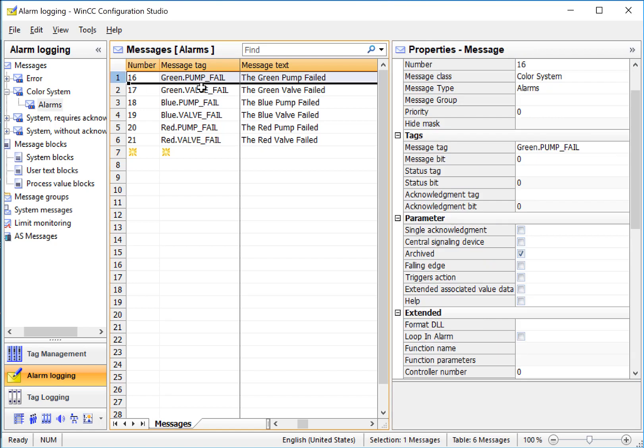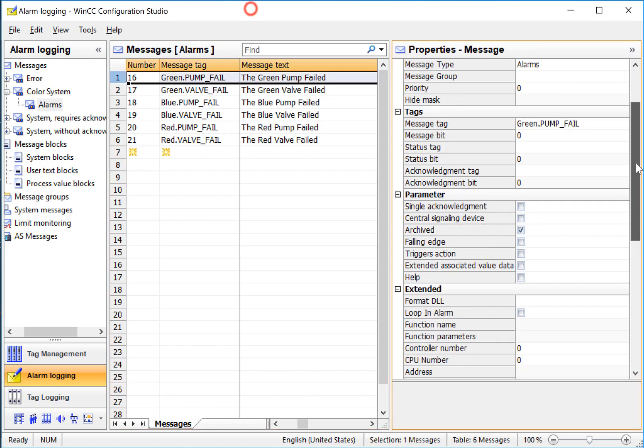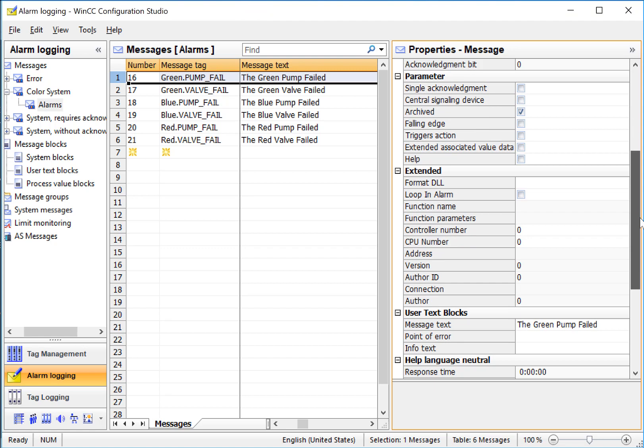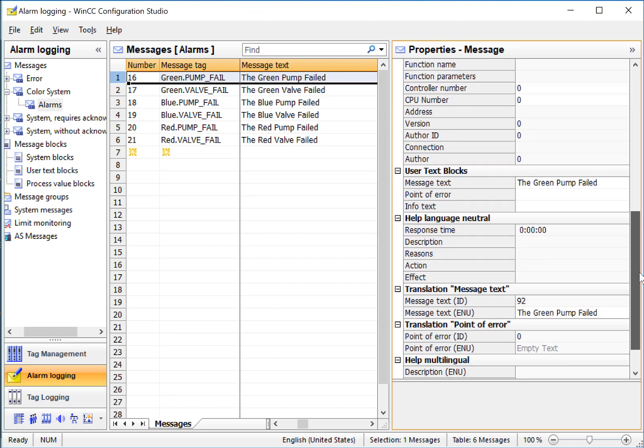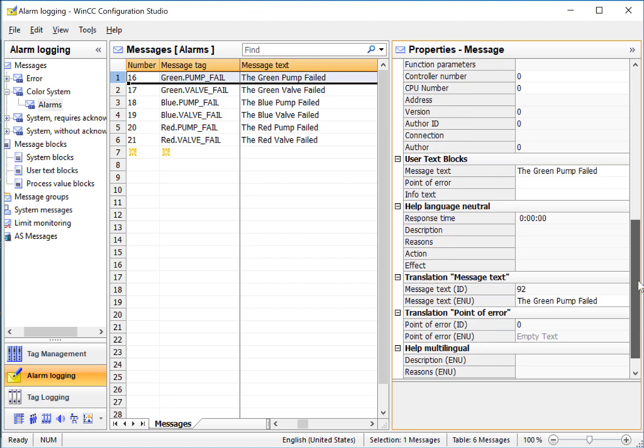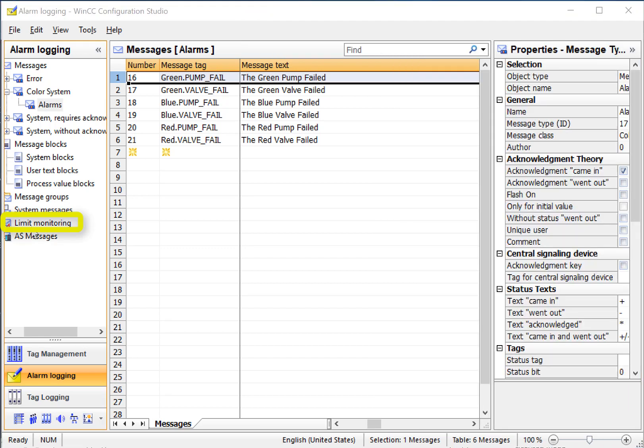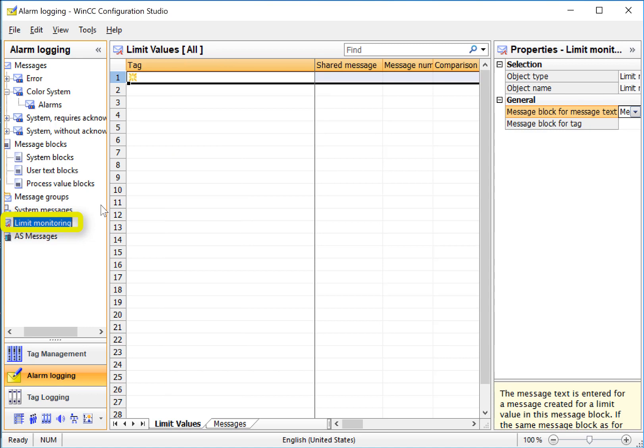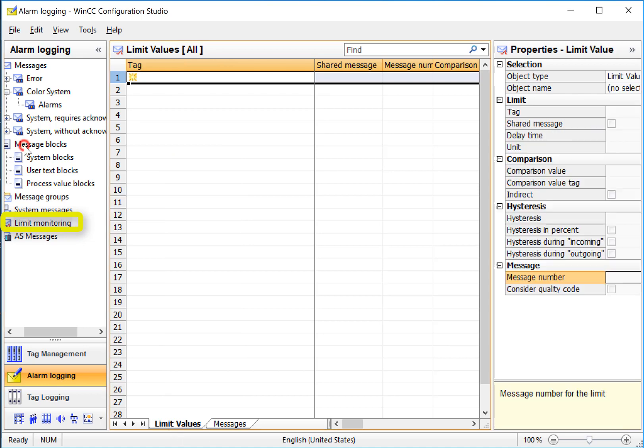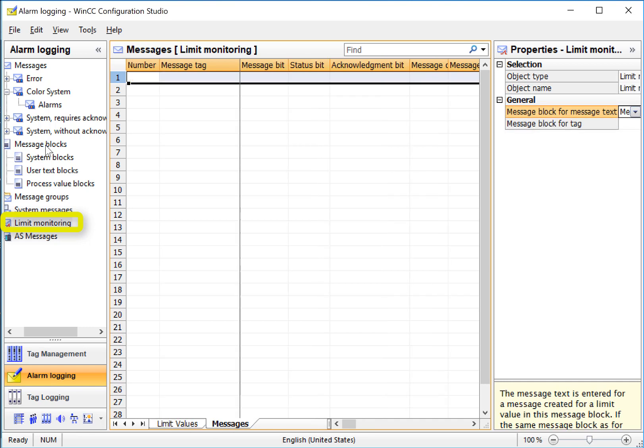You can also set properties of each individual alarm message if you want by going to the properties dialog. Now let's create our analog alarm. We'll go to limits monitoring. And in the work area, we have a limit values tab where we associate the tag and assign high and low limits. And we have the messages tab, which is where we configure our messages.